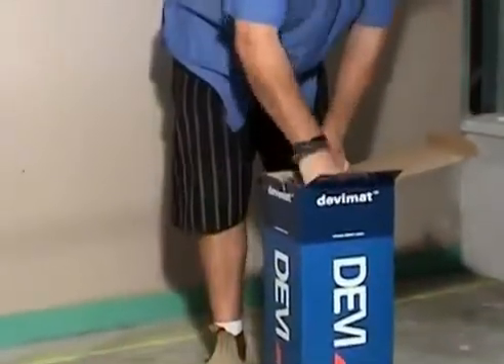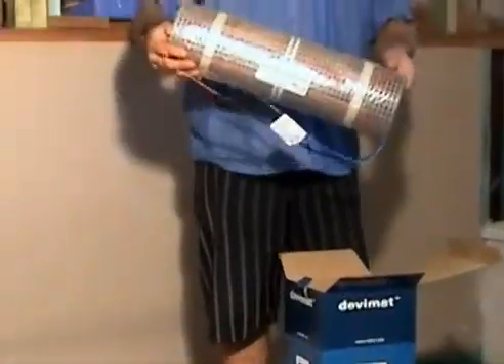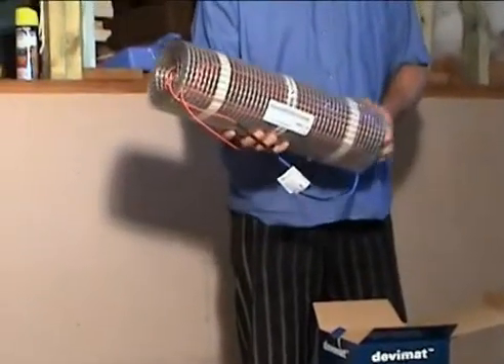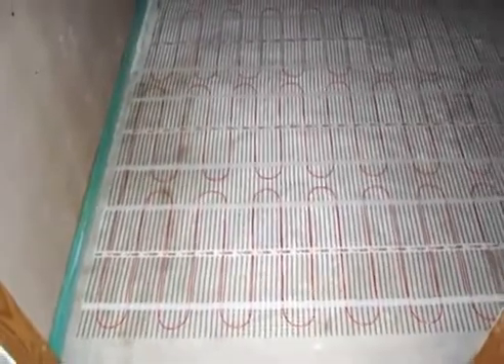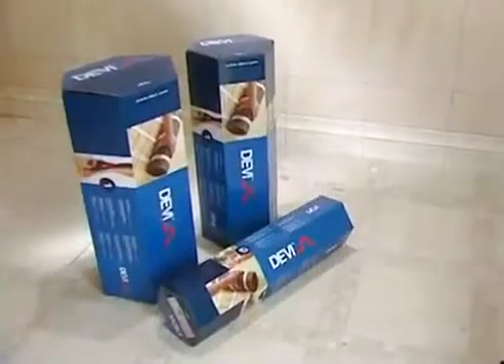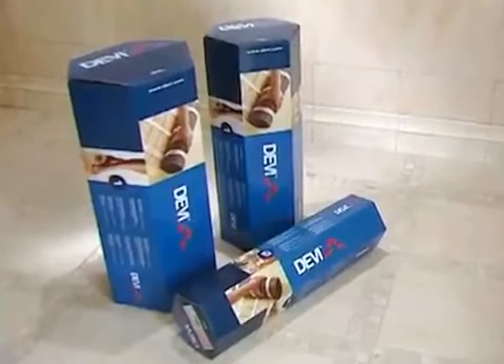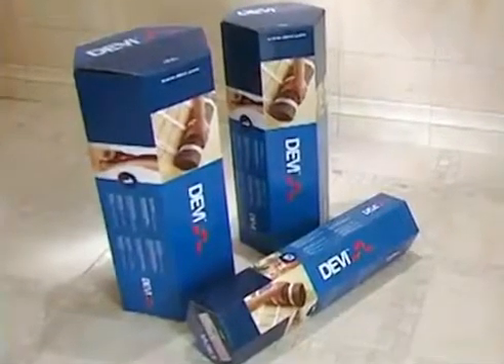You now know what size Devimat you will need. Remember to pick a Devimat that is slightly smaller than the measured area. This will allow the mat to fit easily into the desired heating area. Devimat comes in a range of sizes from half a square metre to 10 square metres.